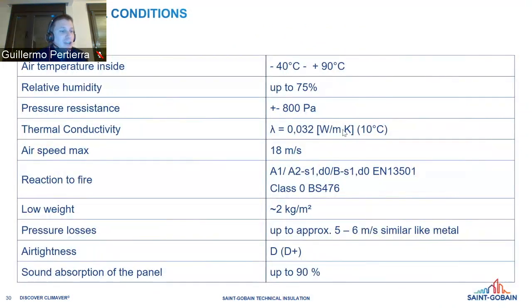Regarding operational conditions, CLIMAVER can be installed with an inside duct temperature between minus 40 and plus 90 Celsius degrees. The maximum relative humidity inside the duct is up to 75%. The static pressure resistance is plus or minus 800 pascals. The lambda at 10 Celsius degrees is 0.032, and the maximum air speed is 18 meters per second.